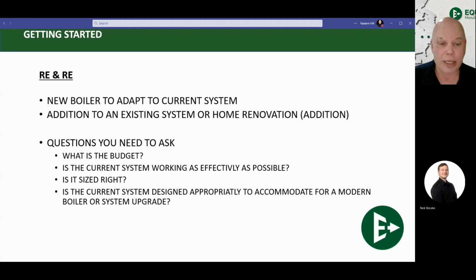Next on the list is: is it sized right to begin with? There's a couple cheat codes you can use with regards to sizing a boiler or sizing your heat emitters, but really what the code dictates is that a heat loss must be done in order to install one of these systems. And it's not just hydronics, this is forced air, this is across the board. A heat loss must be done in order to see if a system is going to be sized right.